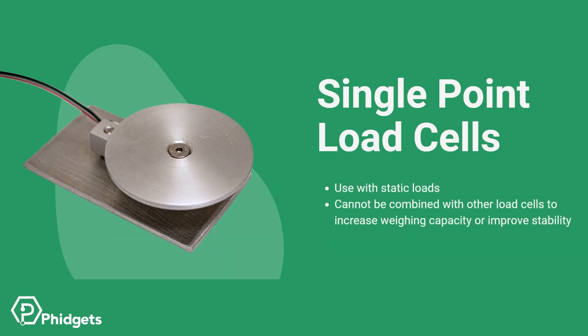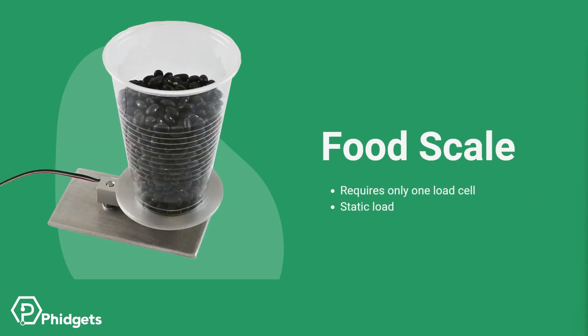These load cells are better suited for static loads. Because of their design, strong impact forces or repeatedly overloading the load cell can result in permanent deformation or even destruction of the load cell. It's not recommended to use these load cells in parallel, which would make the system more complex — there are load cells better suited for that. An example application for a single point load cell is a food scale for measuring the weight of ingredients for cooking or baking.